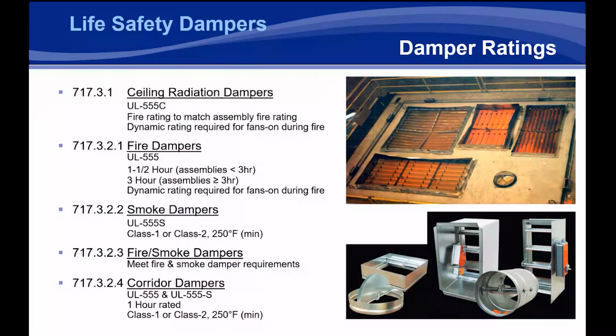For a long time, bathroom fan ventilation manufacturers would have to write letters to explain this to code officials. There's also some problematic code that was added that would close a ceiling radiation damper under detection of smoke to address these issues, to turn off these bathroom ventilation fans. That section of the code is actually being removed for the 27 version of the code because it really used the smoke damper actuation language incorrectly, as ceiling radiation dampers don't have motors, and we'll talk a little bit about that in a second. But the simple thing is, if you've got a bathroom fan that has a damper approved with it and it's listed in a floor ceiling assembly, that product will not create a dynamic system. UL changed their marking guide to fit that.